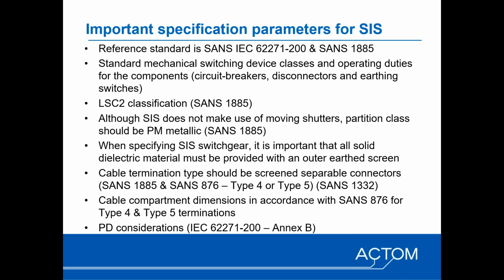While the flexibility is provided by a type 4 outer cone separable screen connector, it is very convenient in terms of being able to plug cables back to back onto one another to accommodate multiple cables per phase. One has to be very sure that you provide proper cable support because of the mechanical strain that could be placed on the outer cone bushing.